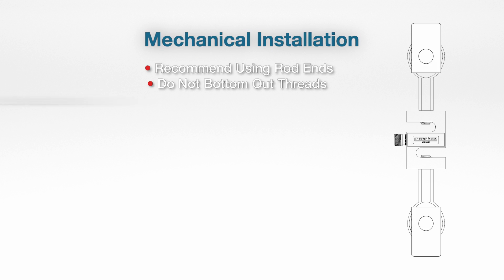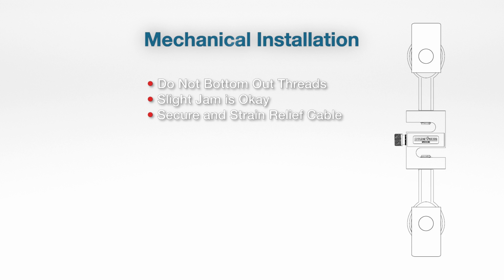Okay, so installing this load cell, much like Brian discussed a little bit earlier, we want to have this installed in the load string such that we're minimizing the potential for any bending moment. This load cell is a little more susceptible to bending moment than the low profile series due to the lack of moment compensation. But again, very highly performing, provided we're minimizing those bending moments. We would recommend, in installation, jamming lightly on the flexure, and then obviously some rod end bearings or something to minimize those bending moments. With this load cell, it's important to make sure that the live end and dead end are oriented correctly. We'll have an illustration coming up next that'll illustrate that a little more. And then strain relieving the cable and securing it in some way, so we're not cycling that cable and potentially fatiguing it.